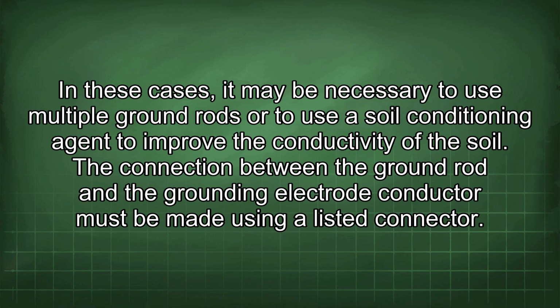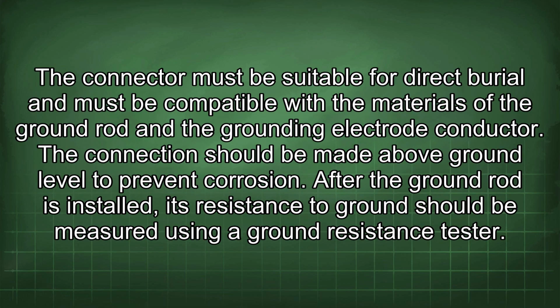The connection between the ground rod and the grounding electrode conductor must be made using a listed connector. The connector must be suitable for direct burial and must be compatible with the materials of the ground rod and the grounding electrode conductor. The connection should be made above ground level to prevent corrosion.